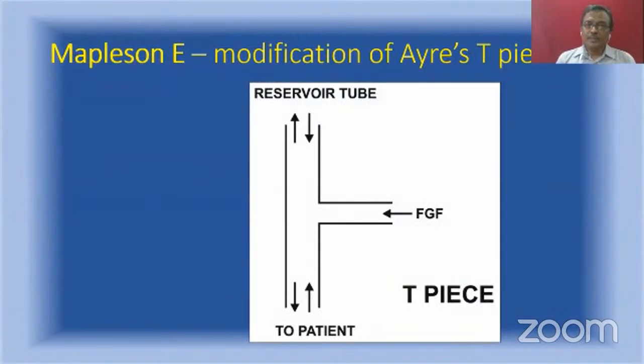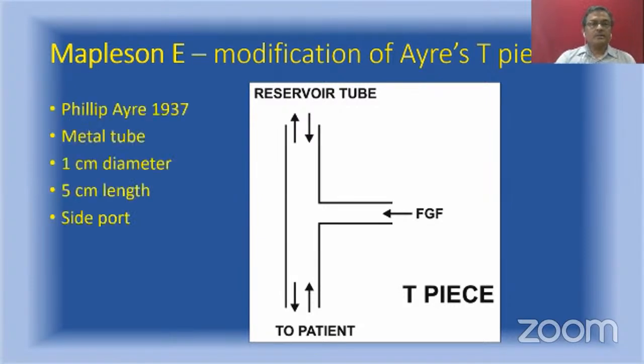Now we move on to Mapleson E circuit, which is the modification of Ayre's T-piece. I said Ayre's T-piece was invented in 1937. This is the original Ayre's T-piece. You can see it was invented in 1937. It is a metal tube. The diameter is about 1 centimeter and its length is about 5 centimeters. And there is a side port you can see through which fresh gas is entering. And through one limb, gas goes towards the patient, and through the other limb, gas will be going out. You can call this limb the expiratory limb and this limb is the inspiratory limb.